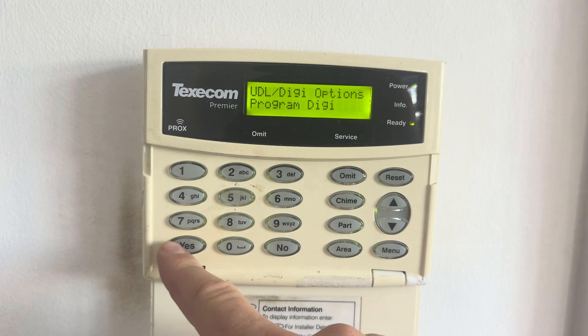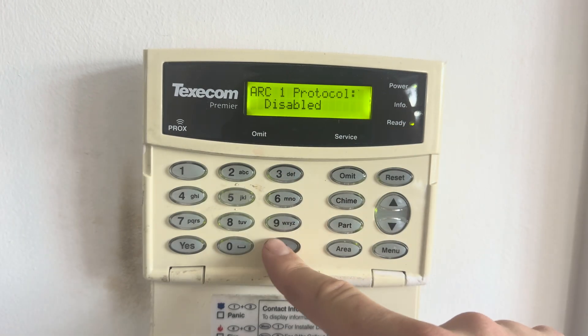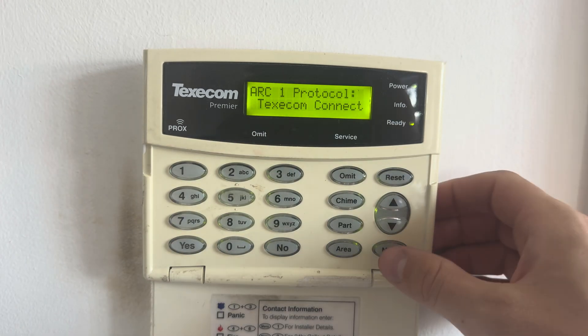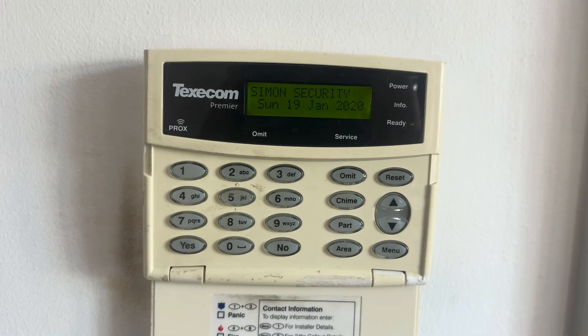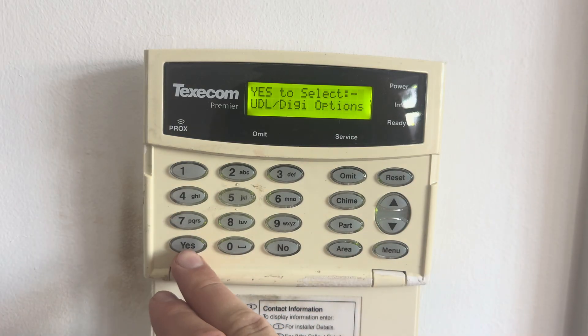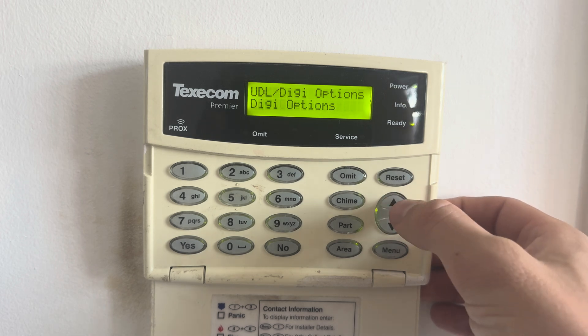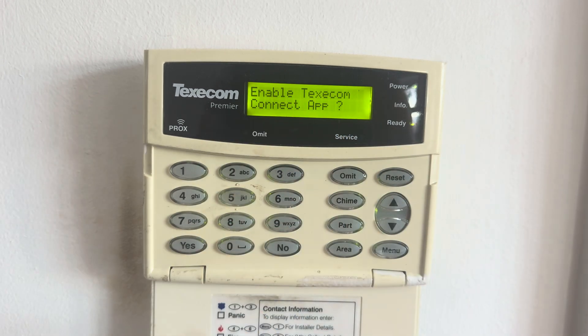Then scroll to Program Digi and press yes. ARC1 protocol will show as disabled — press no, then press up until you see Texecom Connect, and press yes. Now come out of engineer mode. To confirm you're connected to the network, go back into engineer mode, press number seven, press yes, and scroll up until you see 'Enable Texecom Connect App'. Press yes, and you should see 'Modem's Online' — that's what we want to see.